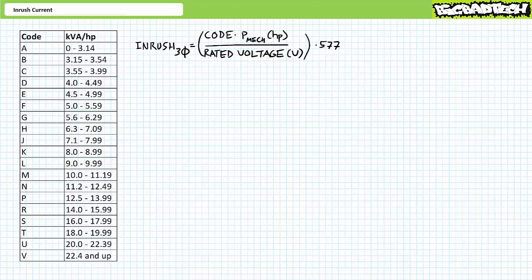As you're no doubt aware, a motor at rest experiences a momentary surge of current known as inrush, starting current, or locked rotor current when energized by full voltage. Inrush current may be about six times rated current, although in this lecture we'll learn to calculate it more precisely. As the motor comes up to the rated speed, current will drop to the rated value.